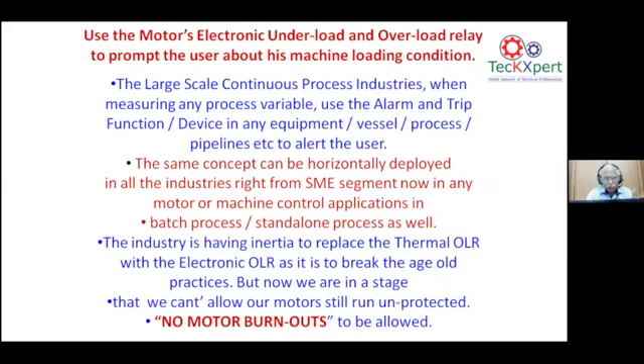You can see, for the given motor, if it is underload or overload, you can have any of the relays, that is, motor protective mechanisms, switchgear mechanisms working in the motor panels. It shows in case of abnormal condition only. Let us try to use this relay, the motor protection relay, as a prompting tool. What is the underload for a given motor? What is the overload for a given motor?